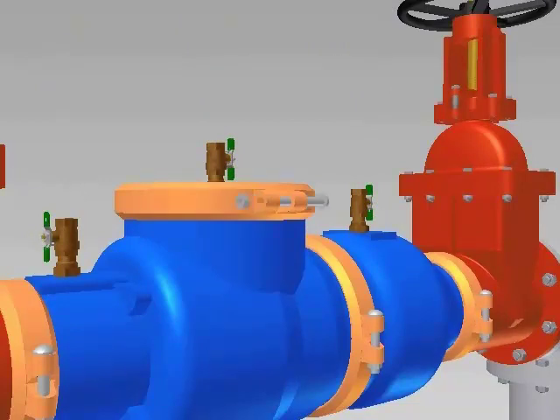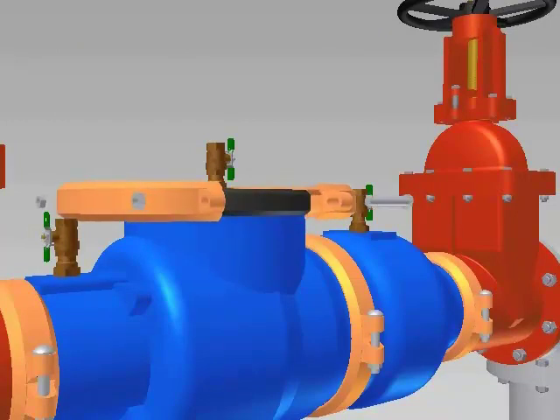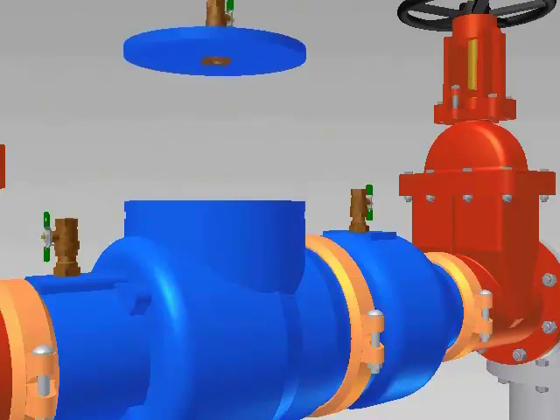Loosen and remove the two nuts and bolts on the groove coupling on the cover. Remove the coupling halves, gasket, and the cover. You can drain the water from the assembly by loosening the cover plate on the bottom of the valve.